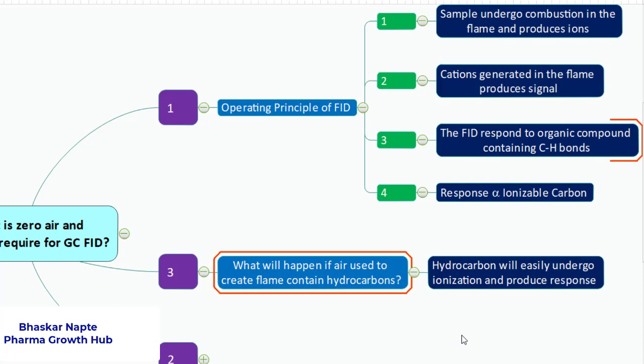Very important point here to be noted: whatever gas you use should not contain any kind of hydrocarbons. And as the quantity of air is too much - we use in terms of 400 ml, 350 ml per minute, a very huge quantity of this air - air can contribute significantly to the detector noise if that air contains hydrocarbons.